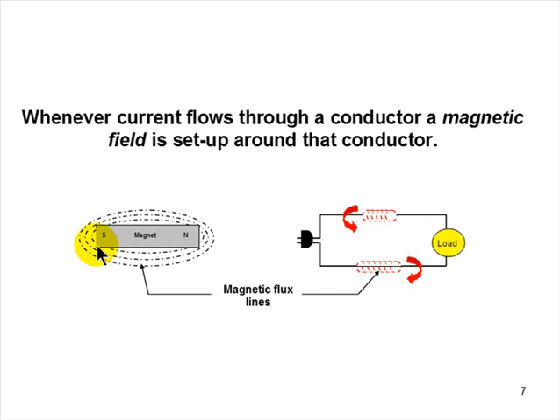In fact, if you were to take a magnet and look at the magnet relative to metal collection, like let's say we're cutting and threading pipe, the slag that ends up in the bucket or the box underneath the pipe threader, if you were to throw a big bar magnet in there, you would see all the slag line up like this, north to south. What you're looking at there are the magnetic flux lines from that magnet. And in this case, the magnetic flux is creating a magnetic field around that you can't see because there's no metal there, no metal slag, but you will see when you hold the compass up there, or you will see when you hook up your amp probe, your clamp-on amp probe.